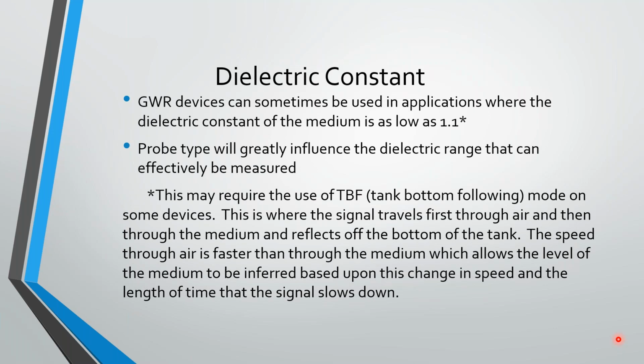Guided wave radar devices, sometimes we can get as low as 1.1. Now notice I've got an asterisk there. This may require the use of something called TBF, or tank bottom following mode. Some devices are capable of this, and with tank bottom following, what happens is the signal travels first through the air, then through the medium, and reflects off the bottom of the tank.